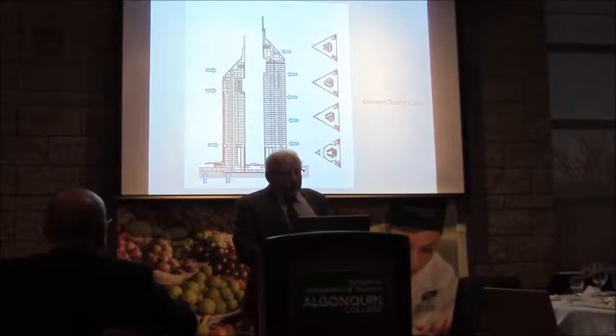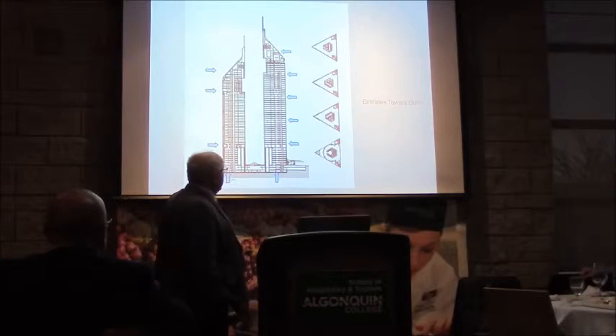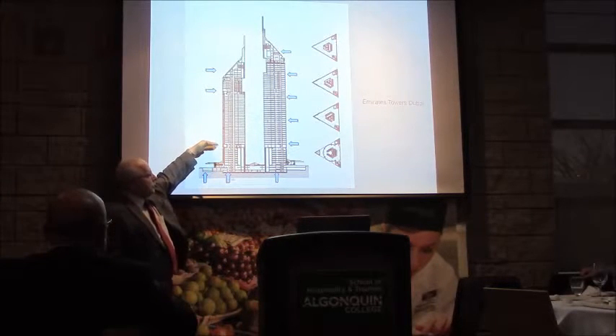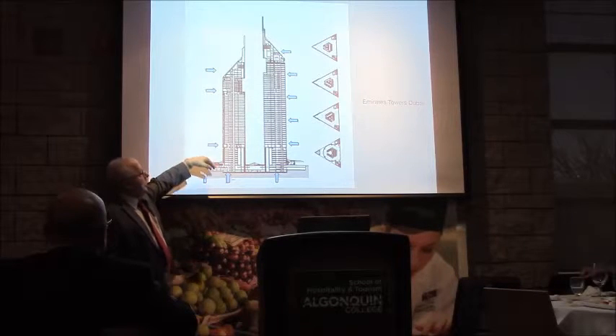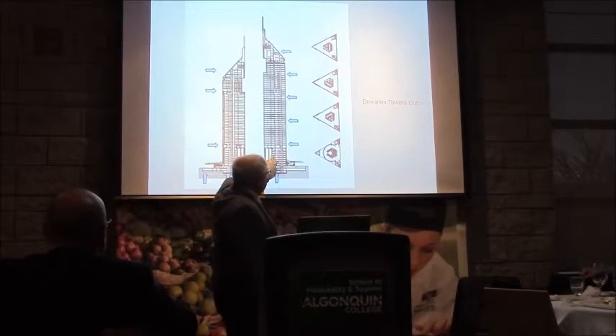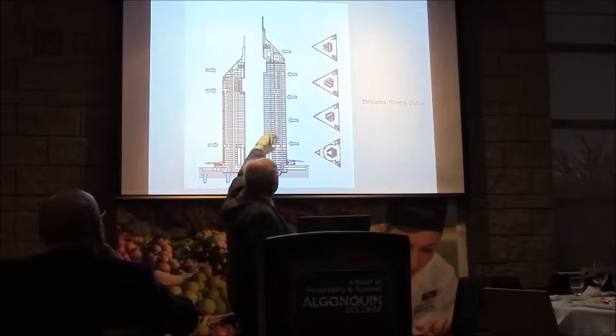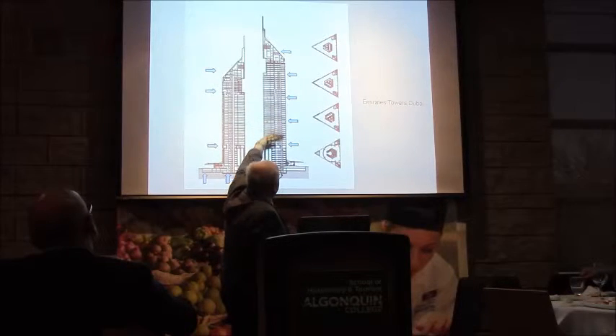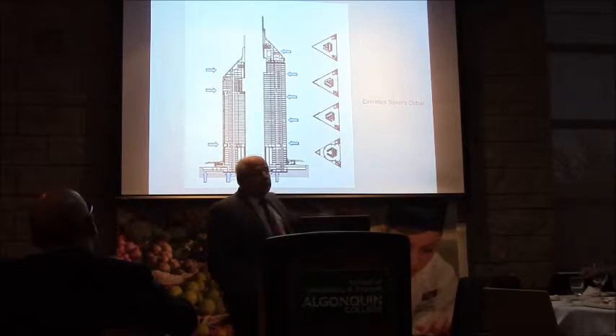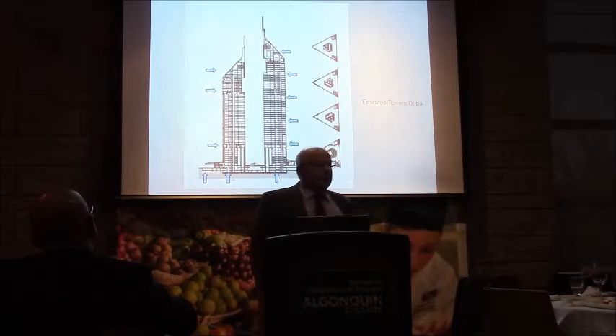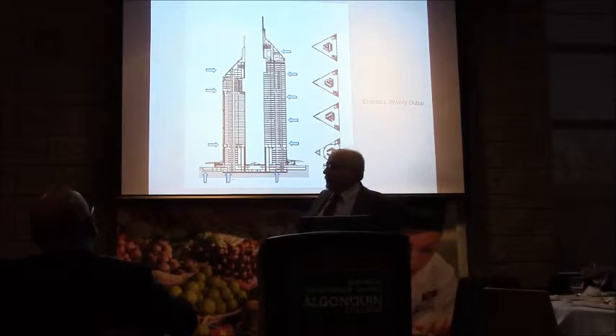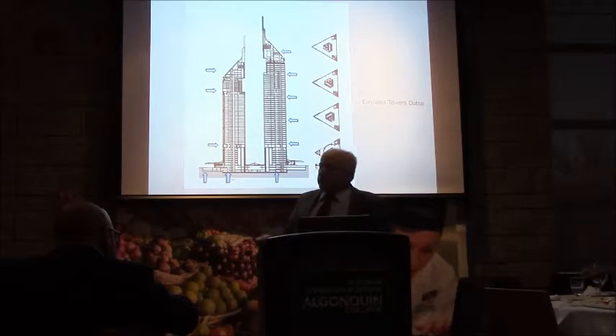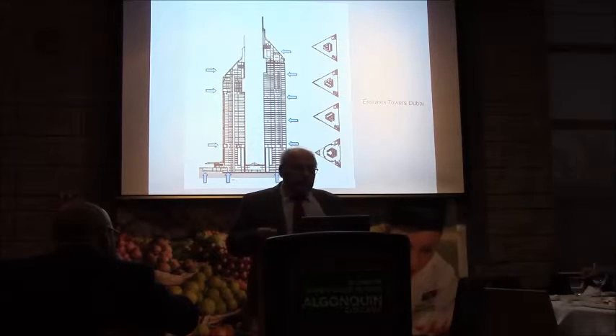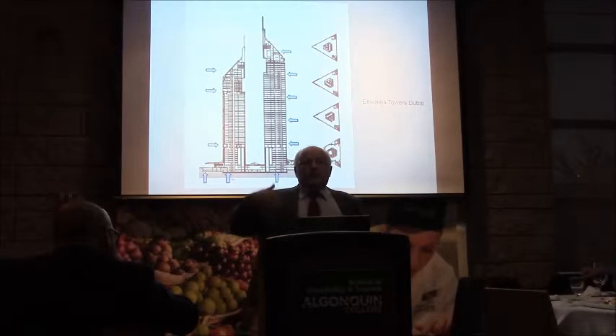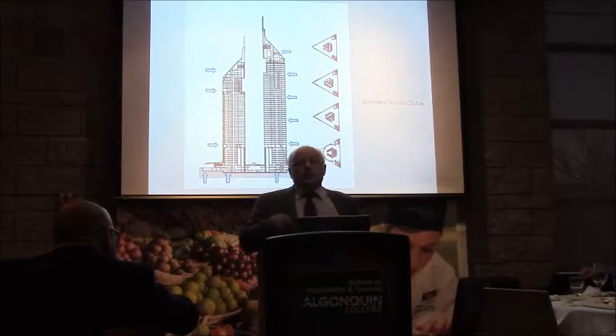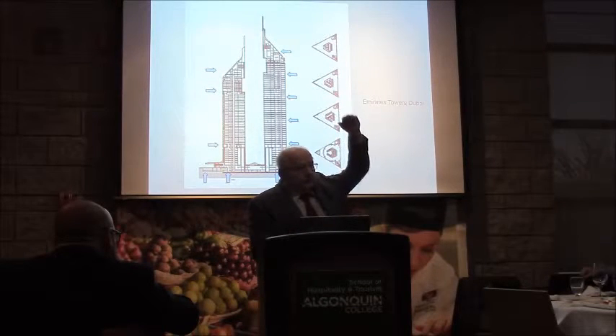On the Emirates Towers, as I pointed out, where these cross bracings occur, we do have mechanical rooms. In the office tower, you can see they're a little bit more regular, and each of these was upfed and downfed from central air handlers that supplied it. But in the hotels, we were talking about fresh air systems, dedicated fresh air with fan coil type systems that did the cooling for the spaces, so the zone could be wider.